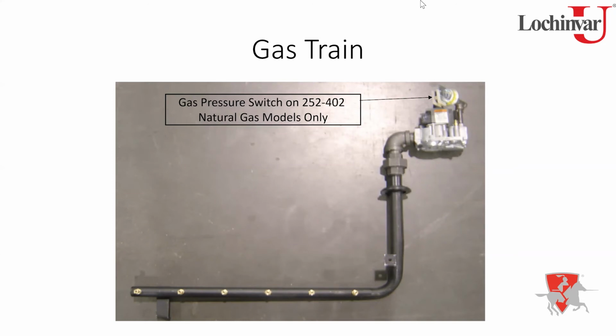Something else that you also see up here on top will be this gas pressure switch. Now you'll notice that is for models 250 to 400,000 BTUs, natural gas only. The only reason that switch is there is to meet a certification requirement. One of the things that we have to go through when we go through our certification is what's called a low inlet gas pressure test. So basically, depending upon what our manifold pressure is, you have to be able to run at a certain minimum number above that. Unfortunately, the models 250 through 400 on natural gas will not pass that test. They cannot fire and run based on this test procedure.